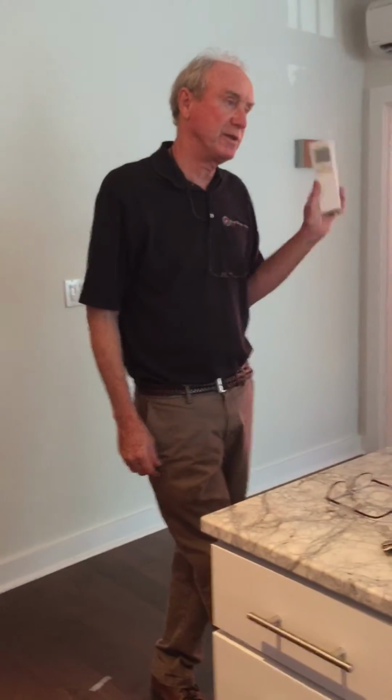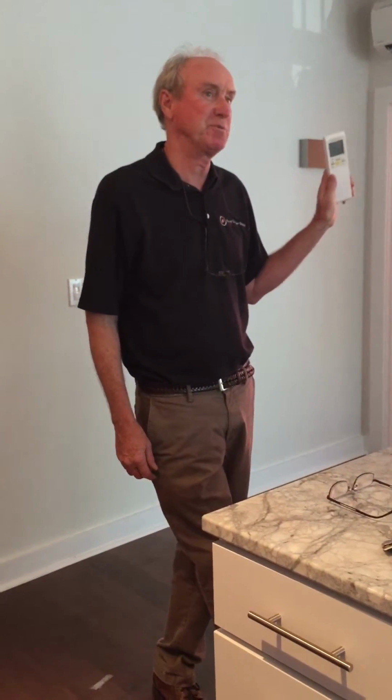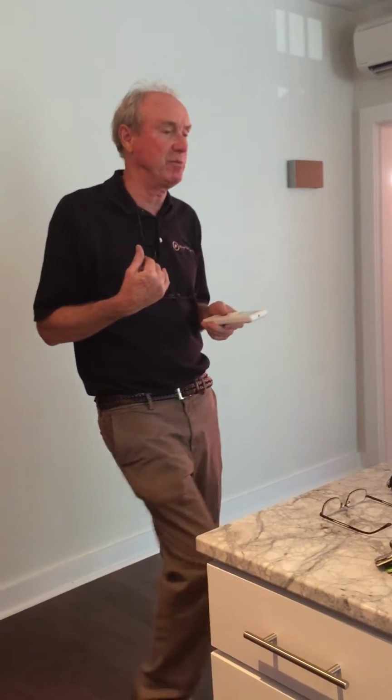One of the reasons that there are beep tones on the Daikin units is because we've had people drive 40 miles for service calls before because an issue is locked in priority and they can't get it going, and it's a new installation and they didn't explain the priority. Some of them didn't even know how it works. If you've got an issue with the priority and you're talking to us on the phone, we're going to tell you to turn them all off and then turn them on one at a time. We can tell what you're doing based upon the beeps, because the phone picks it up really nice.